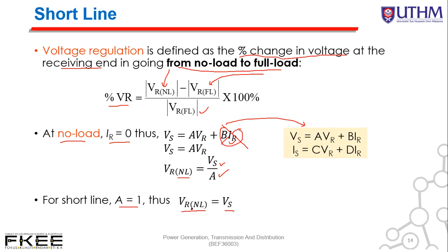So we can calculate the voltage at the receiving end under no load, equal to the sending voltage divided by A. For the short line model, A equals 1. Previously we discussed that A equals 1, B is Z, C is 0, D equals 1. So for A equal to 1, we have the equation for VR no load: the receiving voltage at no load equals the supply voltage. It's clear, of course, there is no load, so the supply voltage equals the voltage of the receiving end under no load condition.